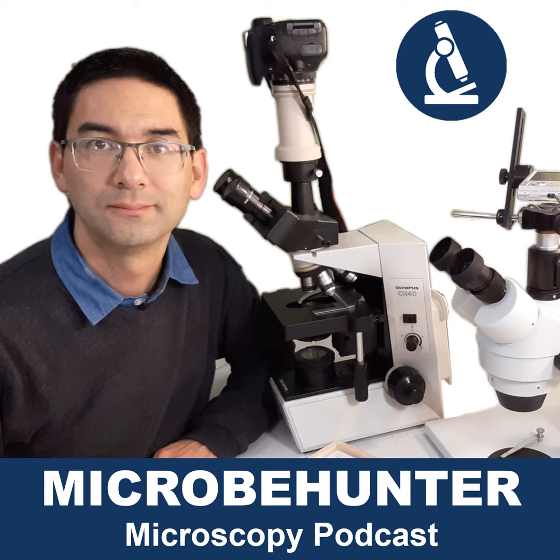The next way that you can increase the depth of field is by completely closing the condenser of your microscope. Closing the condenser has a couple of interesting effects. Yes, it increases the depth of field, so even if they move a little bit vertically, they might still be in focus.